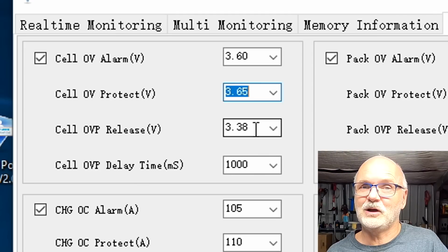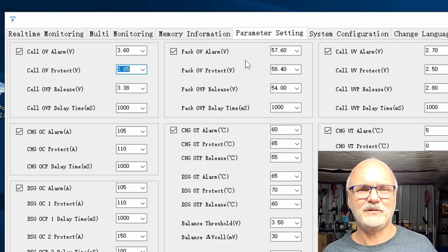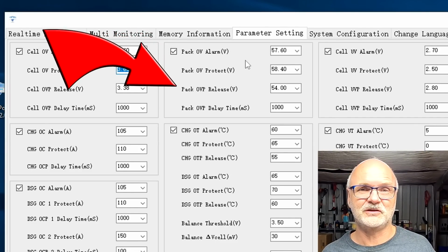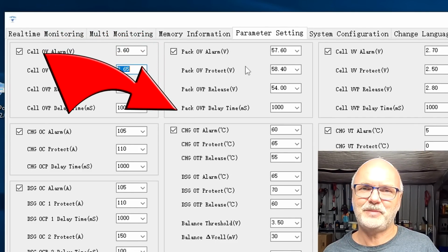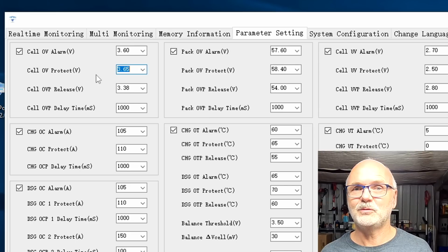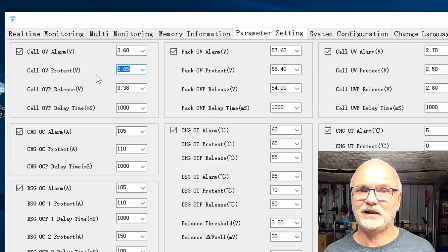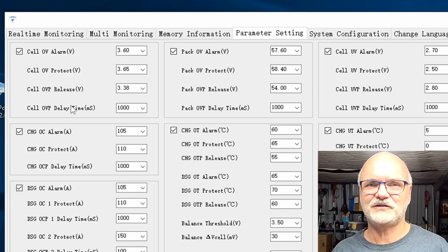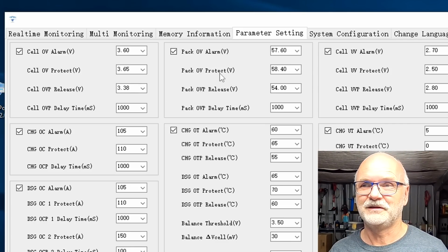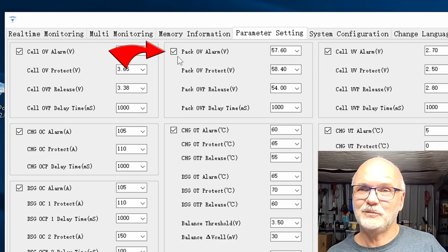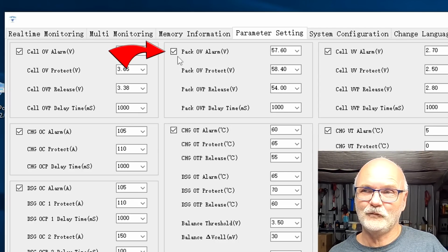And leave your comments down below if your Jakiper battery had the same 3.7 set in the parameters of your BMS, because this is not correct. I don't really see the point why we have Pack overvoltage protection as well, because you can never exceed a Pack overvoltage and stay within normal parameters with your cell settings. It always triggers the cell protection first and never the Pack protection. But with this little tick box up here, we can actually disable all overvoltage Pack parameters and alarms.